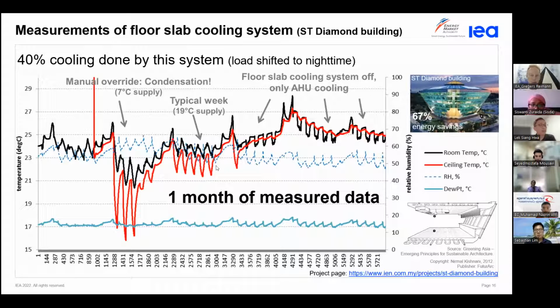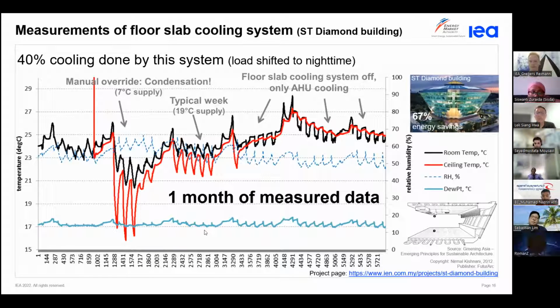And crucially, everyone always asks, does this mean that you have condensation in the building when you cool down the surfaces? But you can see the dew point temperature measured in the space is down here, about 17 degrees. So as long as the ceiling temperature does not drop below the dew point temperature, then there's no condensation happening.